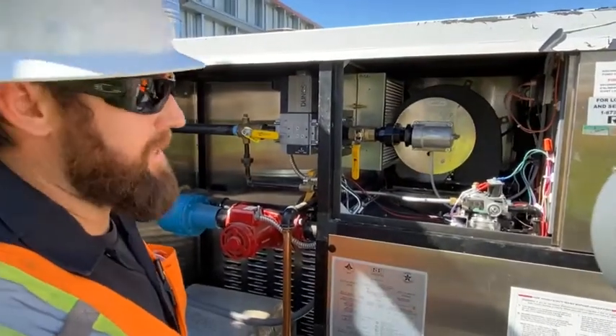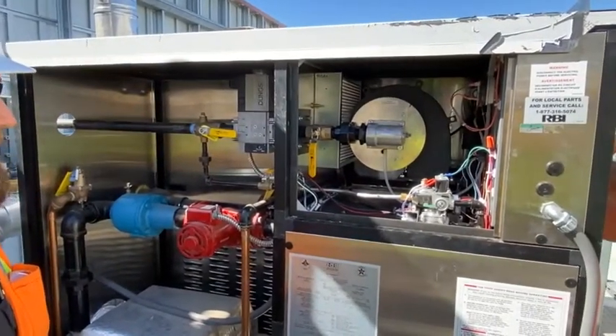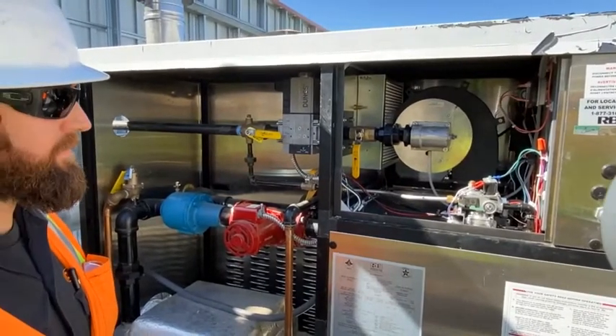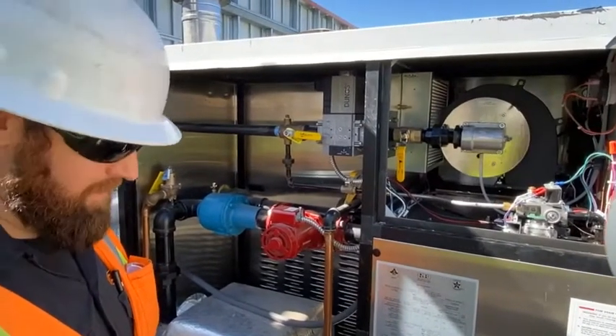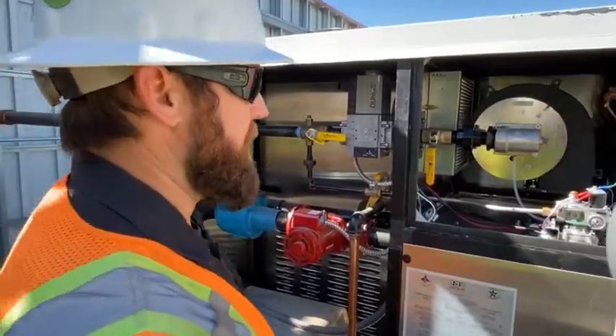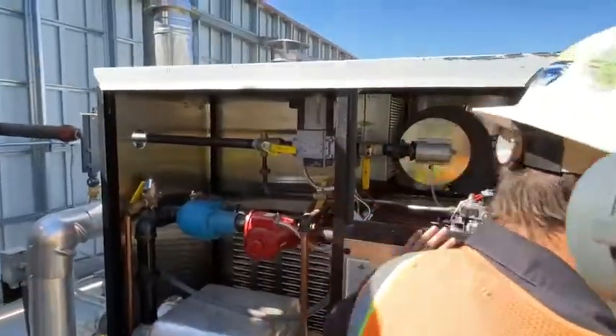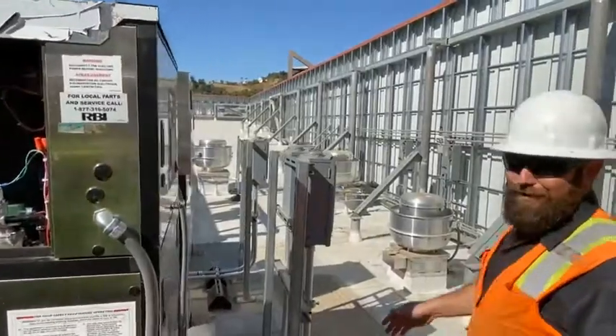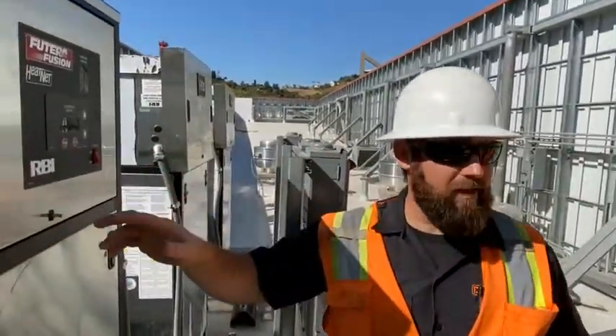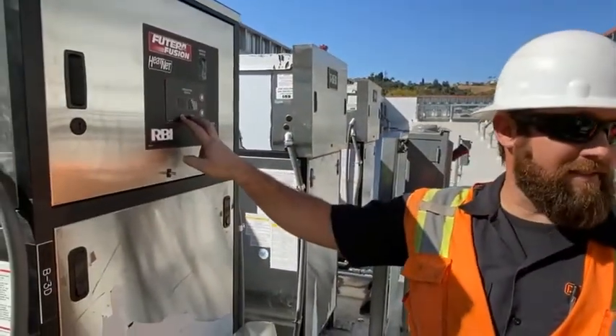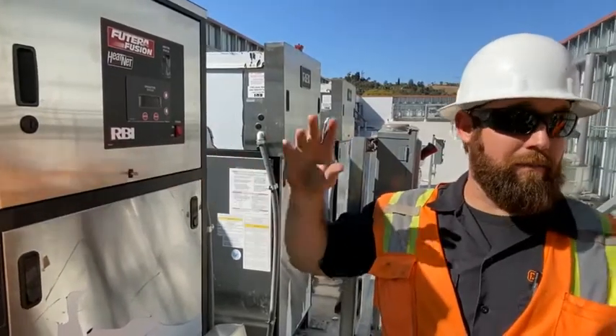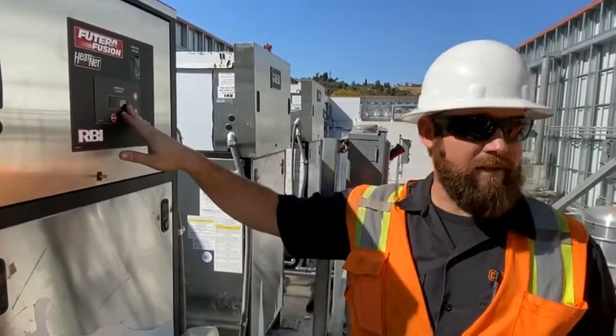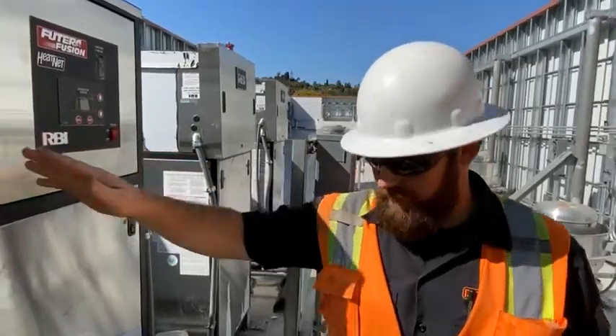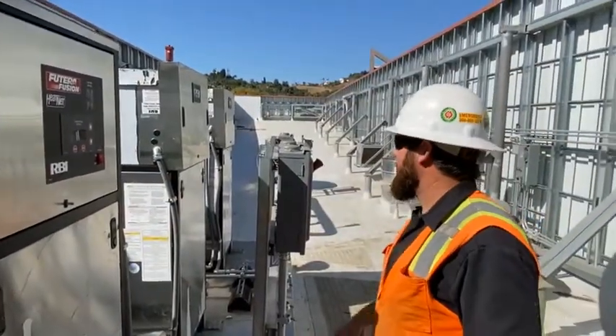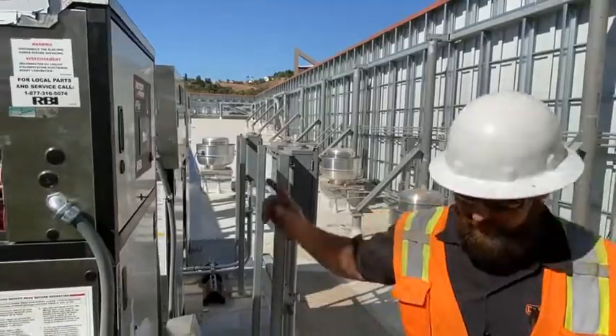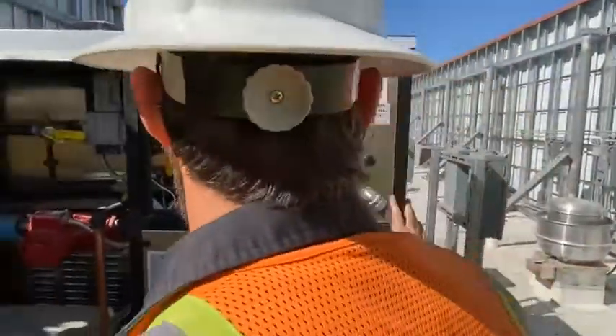Yeah. What does that say on the front display? System and ignition control. Ignition control alarm, exactly. All right, let me show you. I don't really recommend it, but if you're up here doing anything and this beeping is really bugging you, you hold back and select at the same time, and it shuts the beeping off. The alarm is still present, so we'll reset that in a minute. I just want to show you a few things in here. I'm going to have to show you on the far side too in a minute.